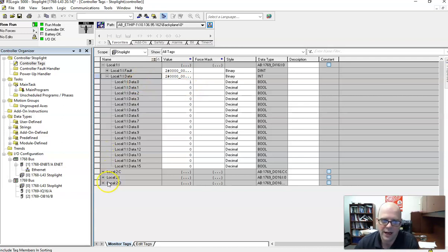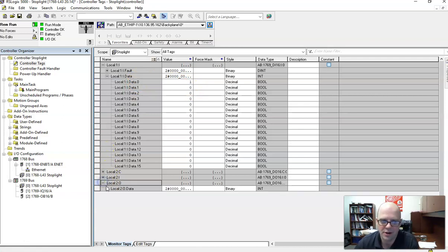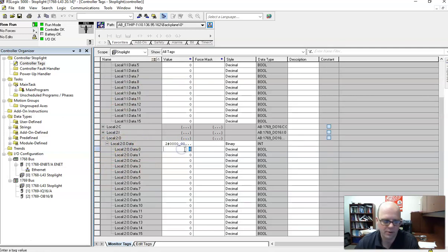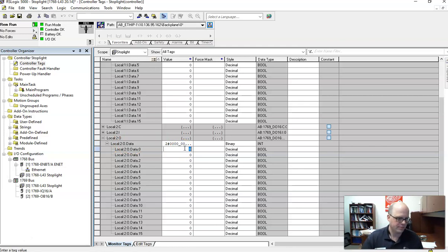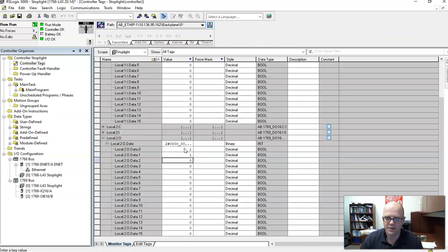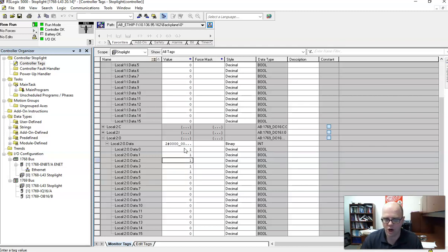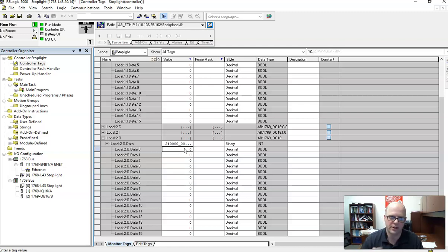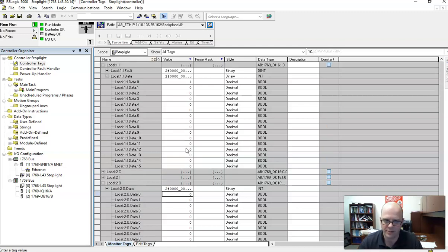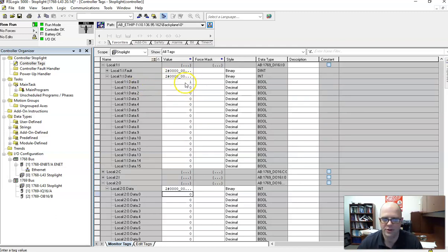For your outputs to test those, we will go down to local, two, O, data, and we will put ones into these spots. And that will turn the lights on according to where we are. If you hit a zero, it turns it off. So literally, I'm just typing in one, and I'll turn that light. And that's why you're testing, because we don't have a program in there. And we'll get to that point eventually. But that's how we're going to test our IO.